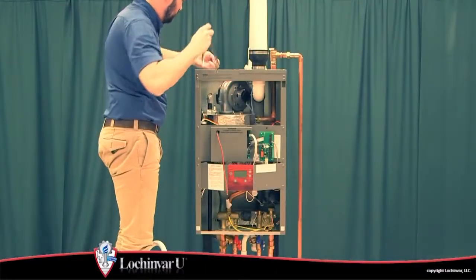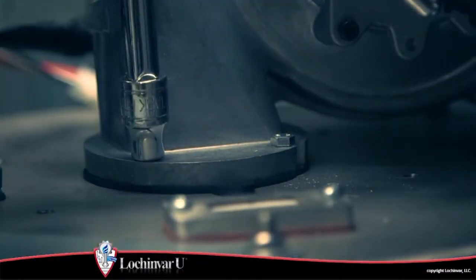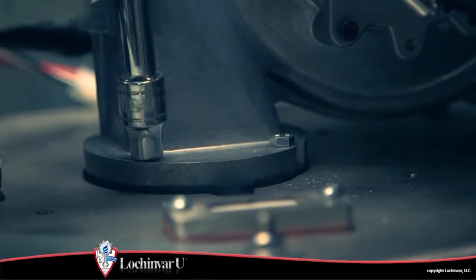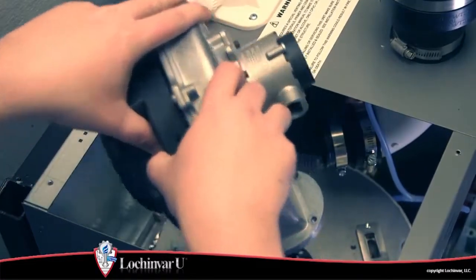Then, using a 5/16 inch wrench or socket, remove the four screws that secure the fan assembly to the heat exchanger top plate. Now remove the fan assembly and Venturi from the unit.